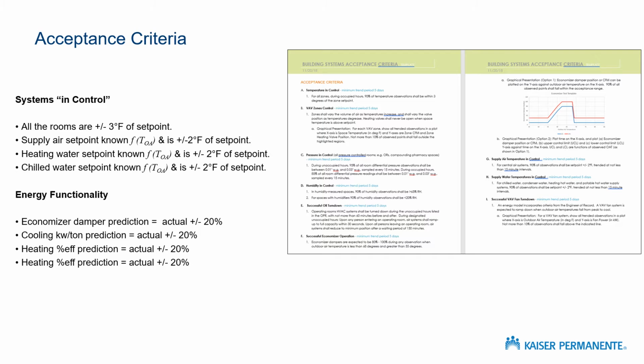Then you have to look at energy functionality. So we need a set of acceptance criteria around energy functionality. And again, those should come out of the design intent. If there's an economizer on the unit, we should be able to look at a few variables and predict the position of that economizer damper. And then we should be able to go measure the damper and boom, it matches, right?